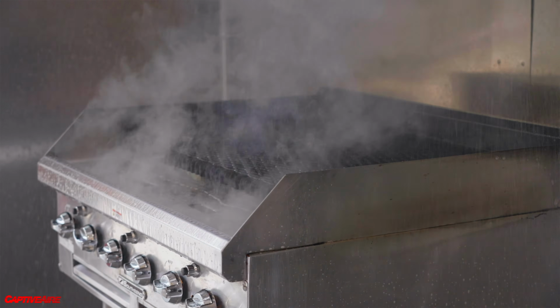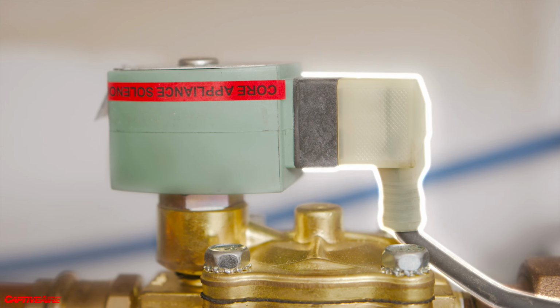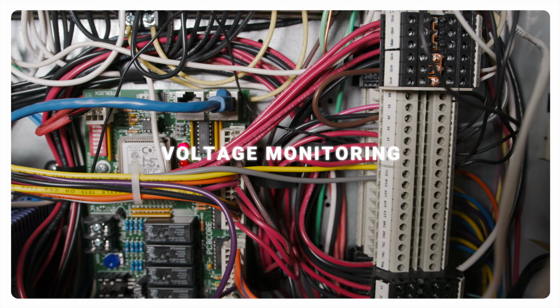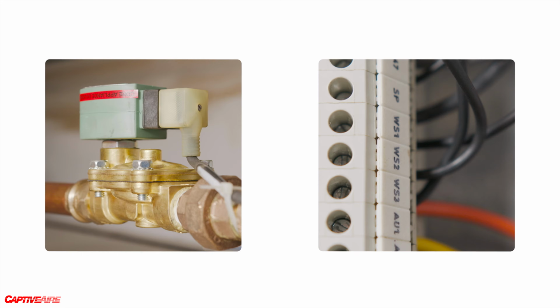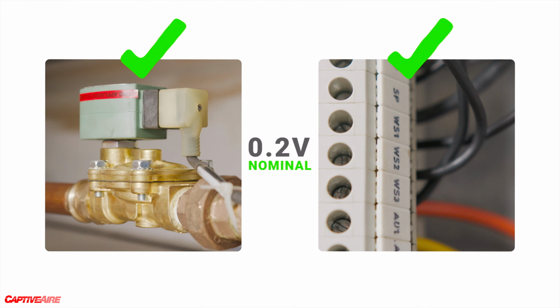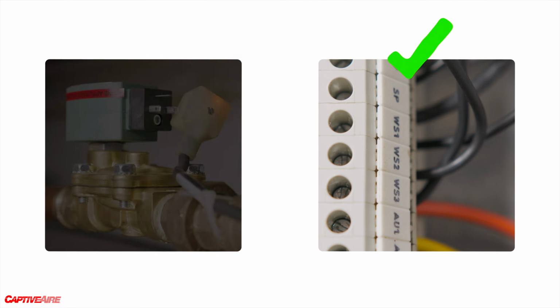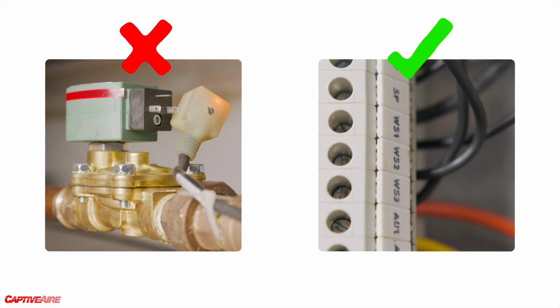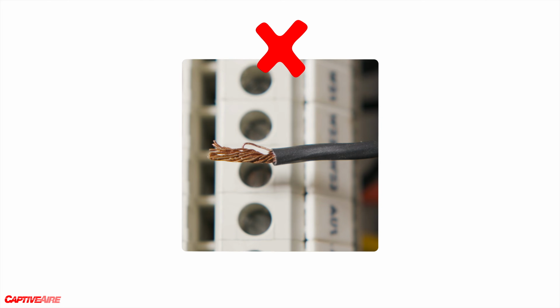One example of supervision is a release solenoid, and the example of how we supervise that is by monitoring the voltage present on that pin. For example, with the solenoid fully hooked up, wired into the board, we'll see about 0.2 volts on that pin, whereas if you pull the DIN connector just off the solenoid, still leave it wired up to the board, you'll see 6.5 volts on that pin. And then if you fully disconnect the DIN cable, nothing wired to the board, you'll see 16.5 volts.